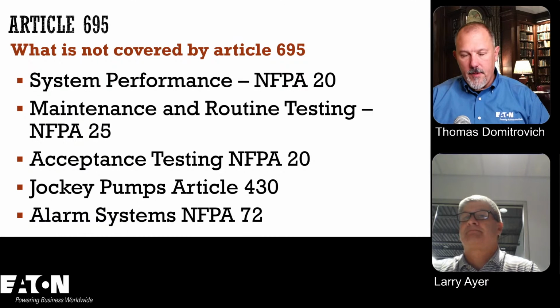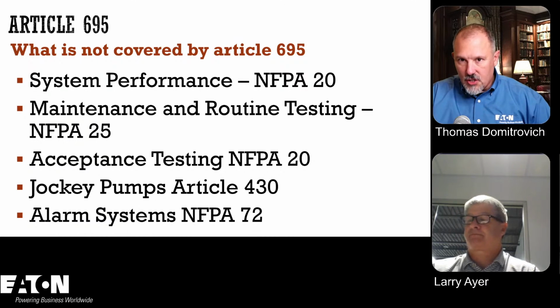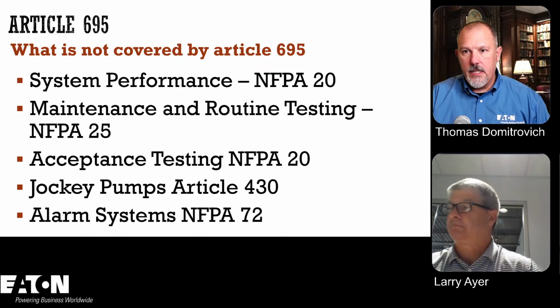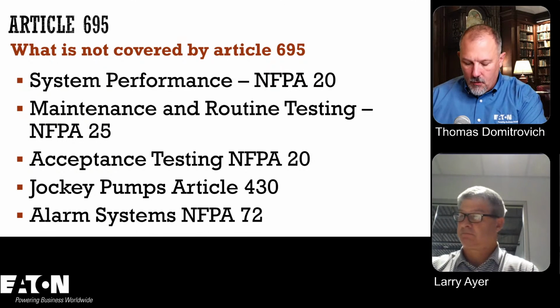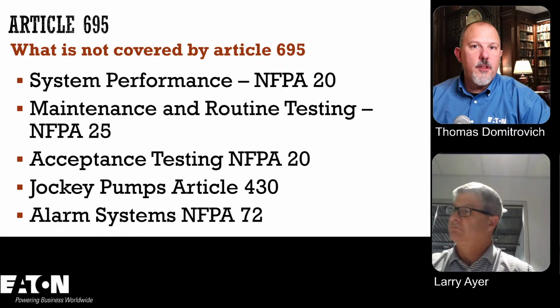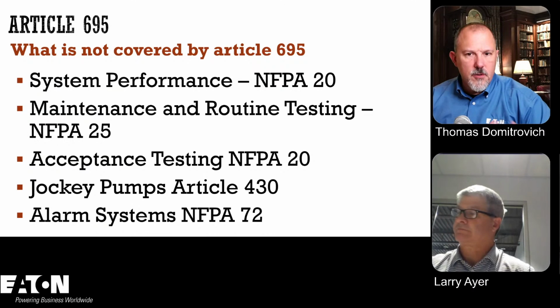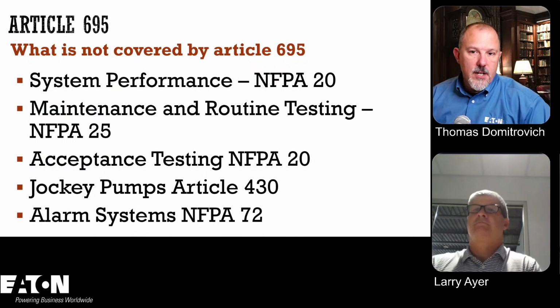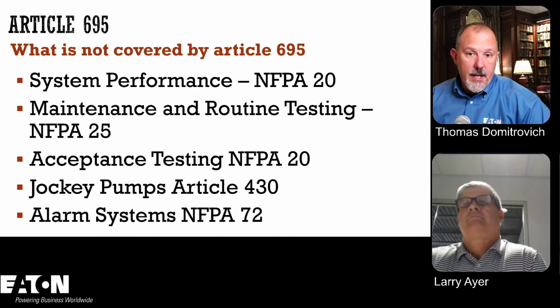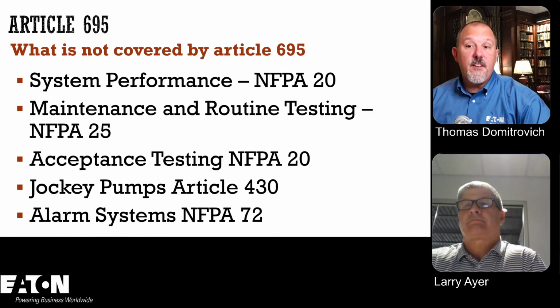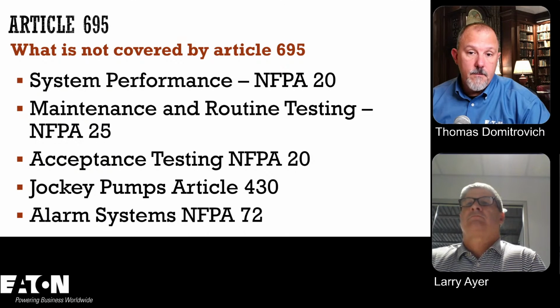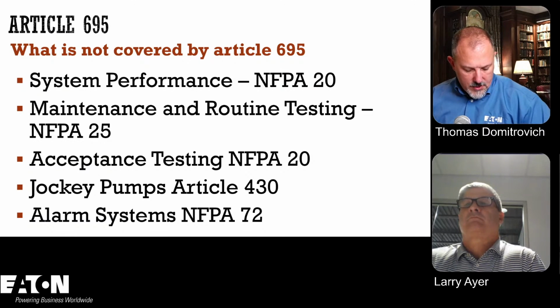Yeah, and it's important to remember that the National Electrical Code is an installation requirement, and then NFPA 20 would be the performance requirements, similar to other documents that have similar relationships. So we already talked about maintenance being in NFPA 25, and acceptance testing is in NFPA 20 as well. So that's interesting that your acceptance testing is in there. We don't have any acceptance testing or performance requirements or maintenance.